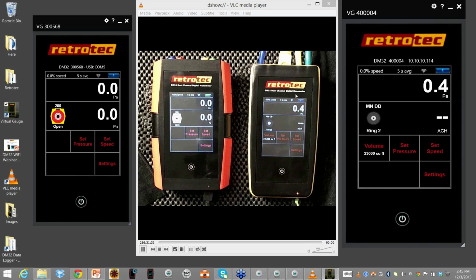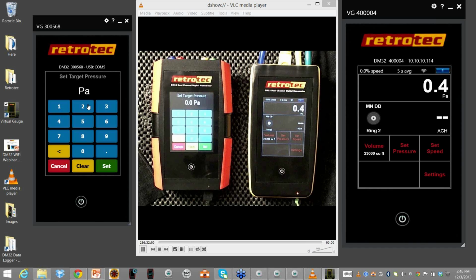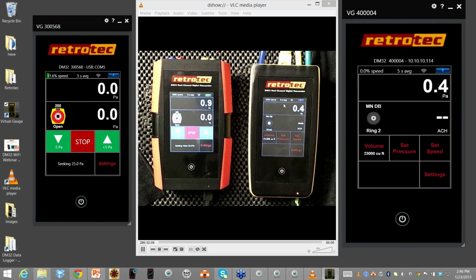If anybody does duct leakage to outside, what I now have set up is a gauge at my blower door and a gauge at my duct tester, and I'm able to run leakage to outside sitting at the kitchen table or counter, controlling both fans from my PC. Over here on the right I have my duct tester, so I can set pressure to 5 — actually it would probably be set to 0 — but on the other side I can set this up for a blower door.